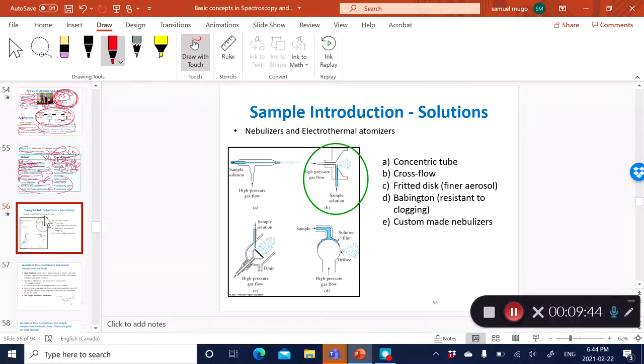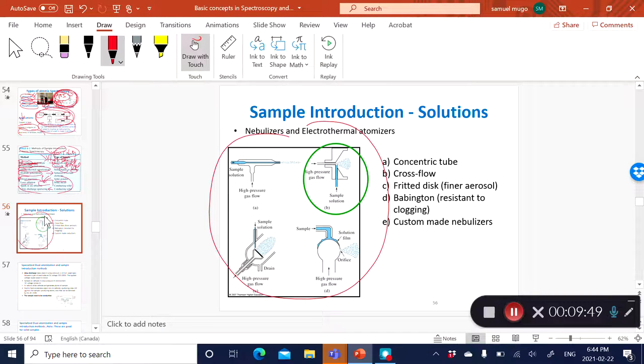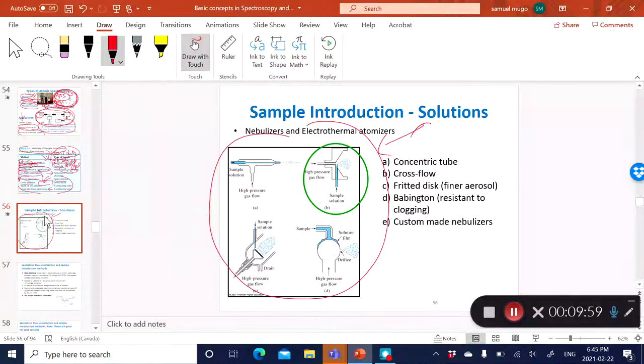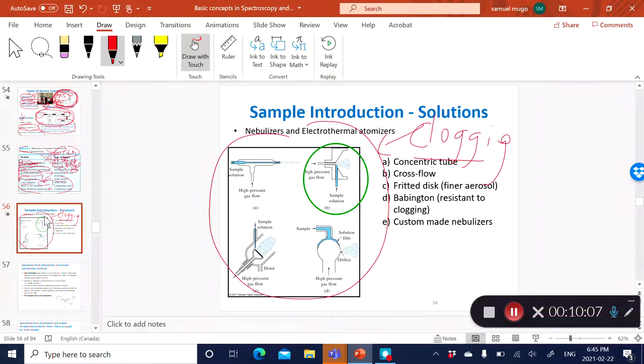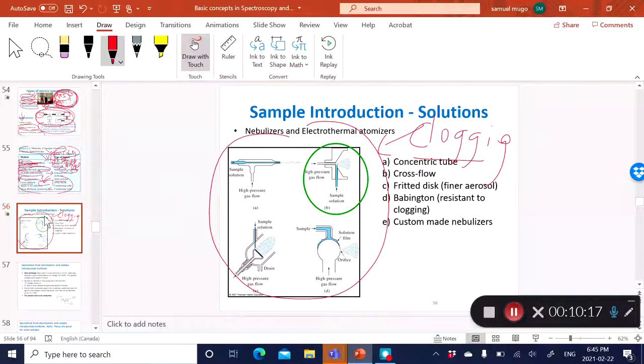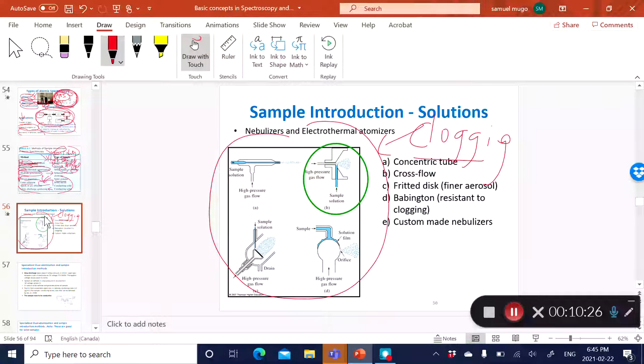With pneumatic nebulization, you can use four or five different types of pneumatic nebulizers. Each one can be fairly resistant to clogging, because one big problem with nebulization is clogging. Clogging occurs when dissolved solids in solution tend to clog the orifice being used for nebulization. Some pneumatic nebulizers have different resistances to the clogging effect.